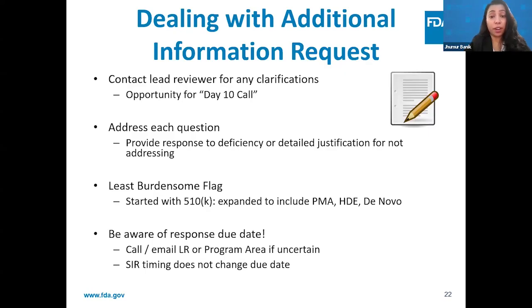And the other thing is to respond to the deficiency questions as clearly as possible and within the response timeline. And then you can use the SIR Q-Sub program, also known as the Submission Issue Request Q-Sub program, to discuss the deficiency questions further. Do note that it is not a pre-review of any potential responses to the deficiency questions, and it does not impact the response due date. There's also the least burdensome flag approach, where you request a review of the FDA reviewer's request for information which you believe may be overly burdensome. And I'll go into further detail in the next slide. So the ultimate thing with the additional information letter or deficiency letter is to respond to the deficiencies, but there are other tools that you can utilize to help guide the response effectively and clarify the questions being asked.